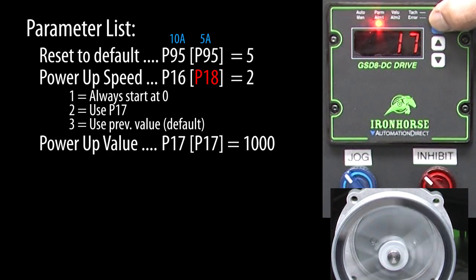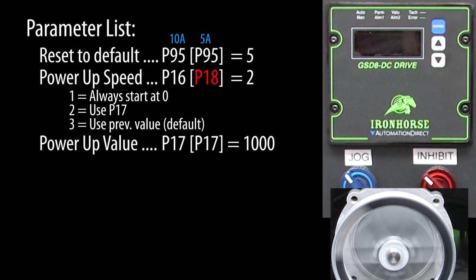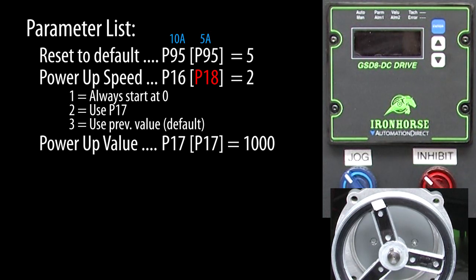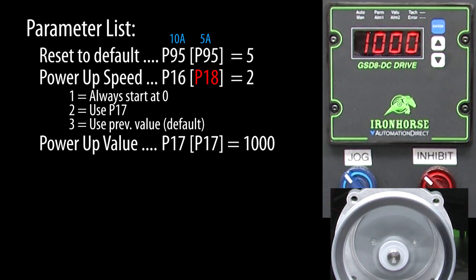We don't actually have to exit the parameter settings. As soon as we hit enter to accept the value, it was done. We are currently at 360 RPM, so if I power down the drive, give it a second or two, and then bring it back up again, it goes directly to 1000 RPM. Exactly what we asked for.